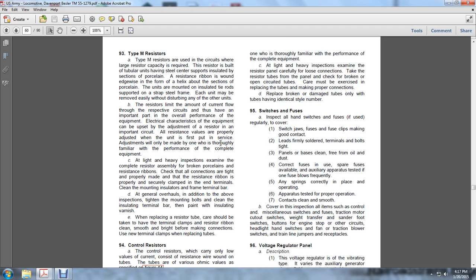95. Switches and fuses. Inspect all switches and fuses, if used regularly, to cover: the switch jaws, fuses, and fuse clips making good contact; leads firmly soldered; terminals and bolts tight; panels and bases clean from oil and dust. Check current fuses and the use of spare fuses. Available auxiliary apparatus should be tested if one fuse blows frequently. Any spring should be correctly in place on operating apparatus, tested for proper operation.